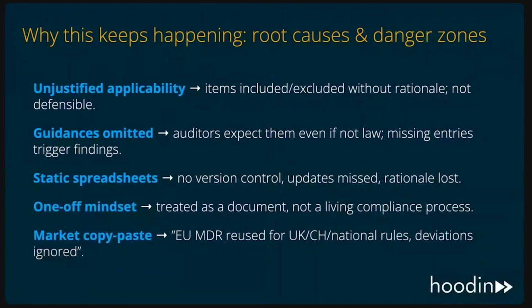Market copy paste. So I also see a lot of companies that use MDR, for example, reused for the UK or Switzerland or national rules, and they don't care about the deviations, or I bet they care, but they haven't realized how many there might be. So there are deviations between any member state and the EU MDR versions, but it would be more than the MDR, of course, and IVDR.